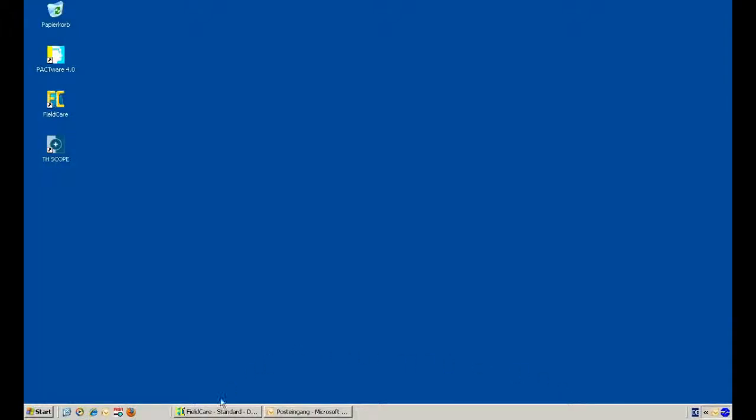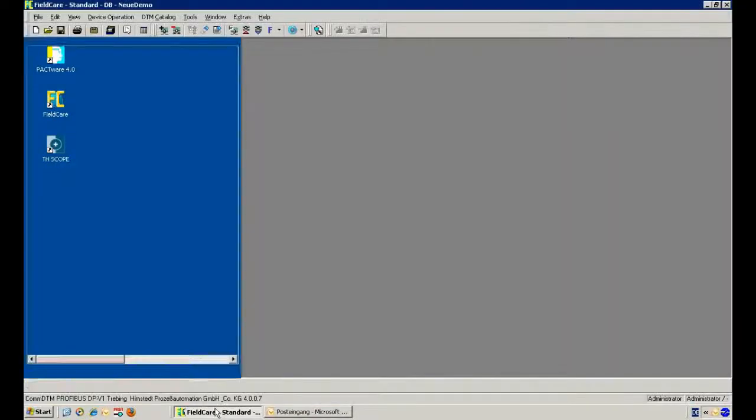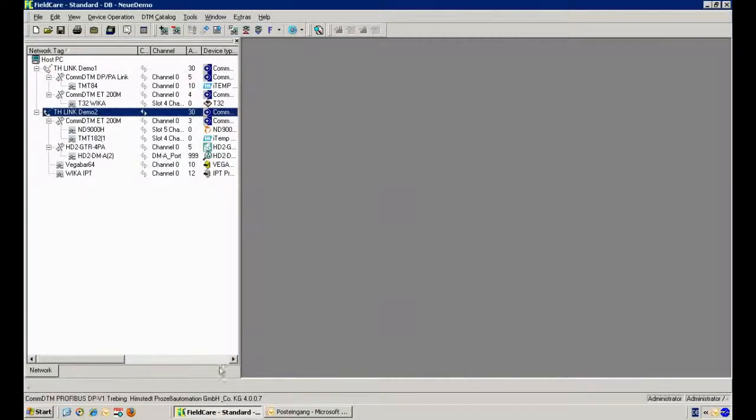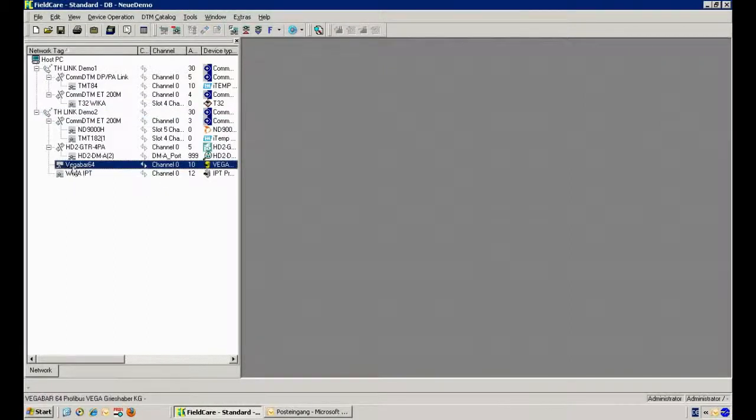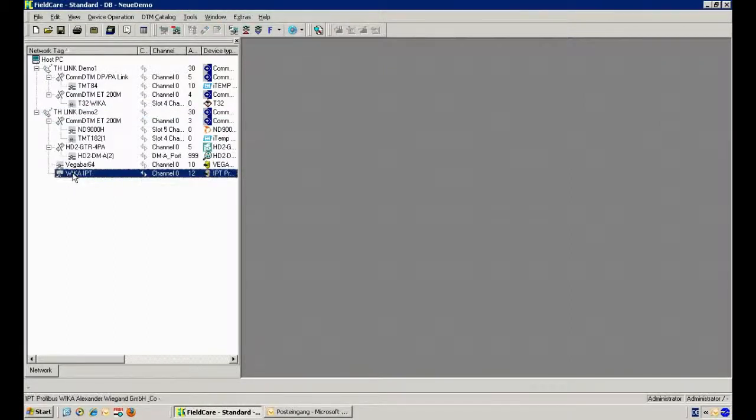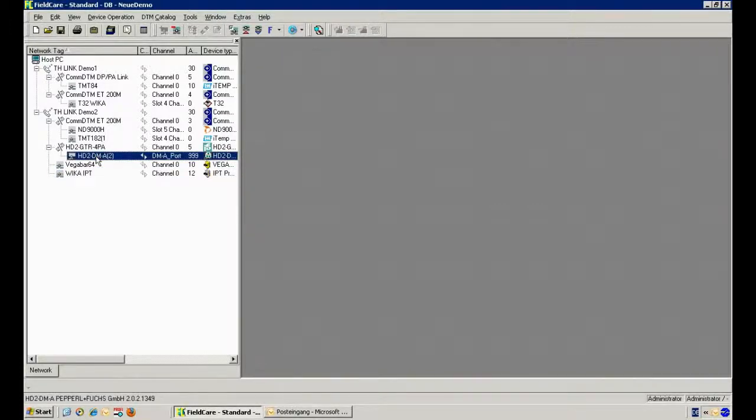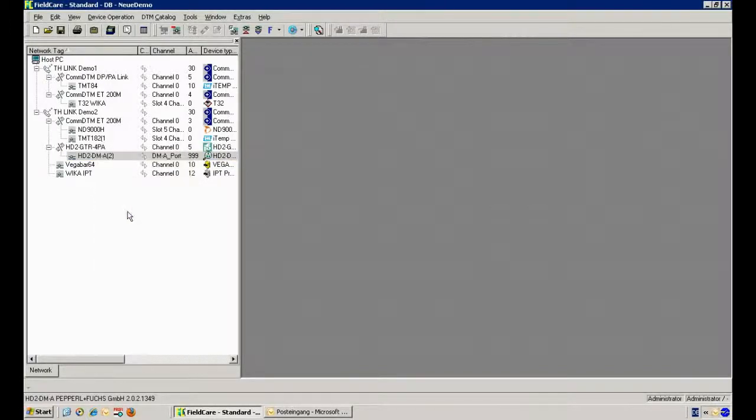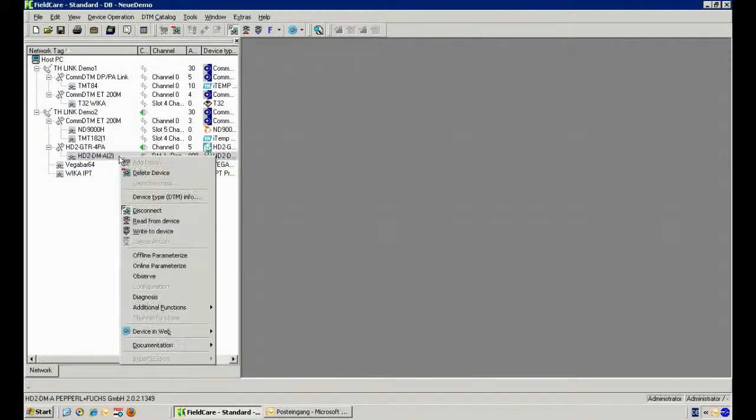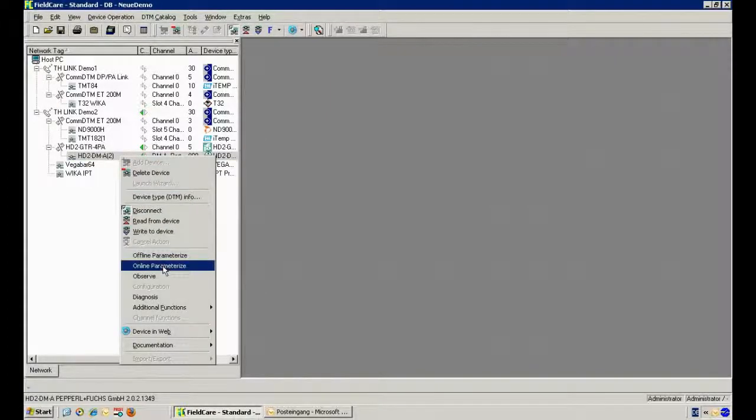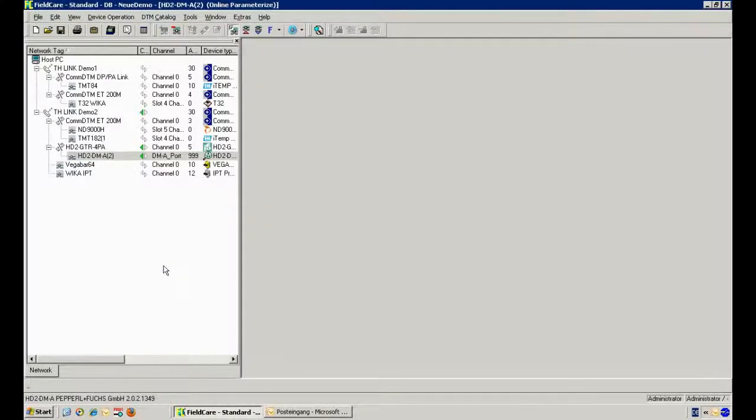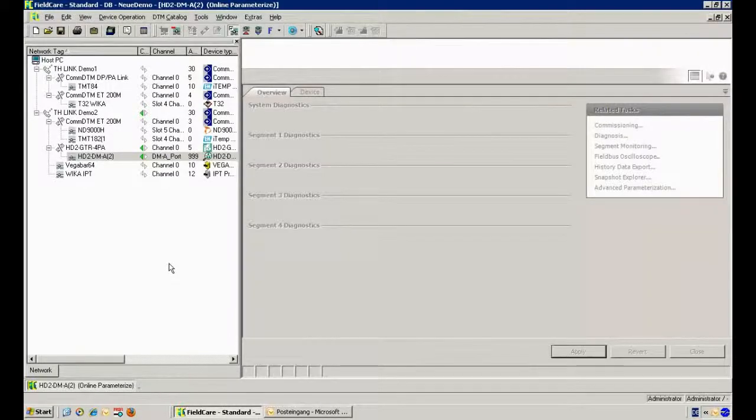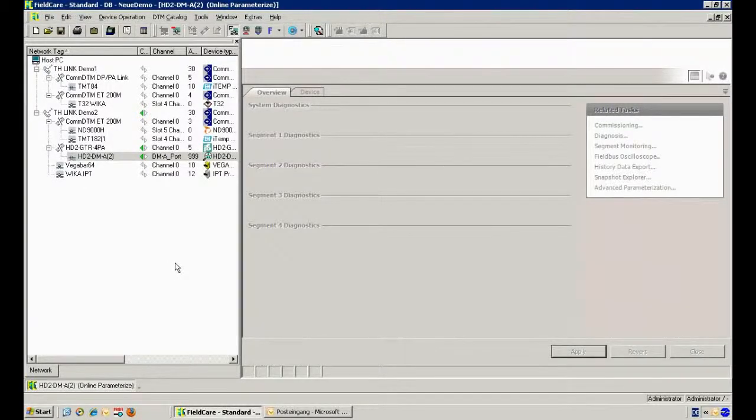We open again our FDT application Field Care and we choose the other TH Link because we know exactly now we have the other network with problems. We see the PA devices behind the transparent coupler and we see the DTM from the Advanced Diagnostic Module from Pepperl & Fuchs, and we will connect now with this DTM to go deeper in the diagnostics on the segment.